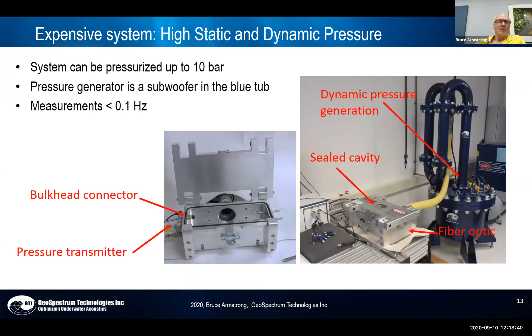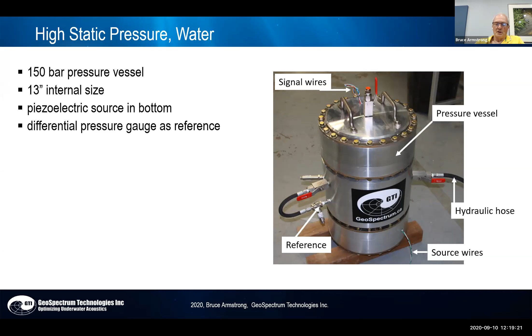Here's the same technique, but in this case you do it in water. I've been talking about air, but this technique works in water just as well. So here's a pressure vessel that has a 13-inch internal size, and it takes 150 bar. There's a piezoelectric source in the bottom, and you again use a differential pressure gauge as a reference. So now you can calibrate hydrophones as a function of pressure down to the limit of the pressure vessel. And the good thing is the reference hydrophone is temperature compensated, so you can do this at whatever temperature you wish as well.